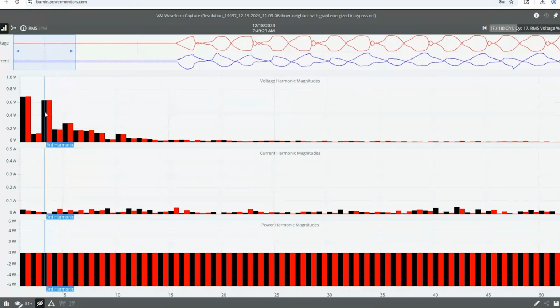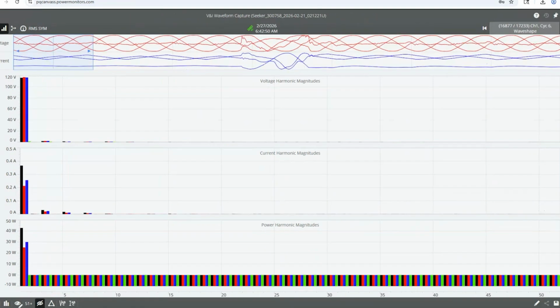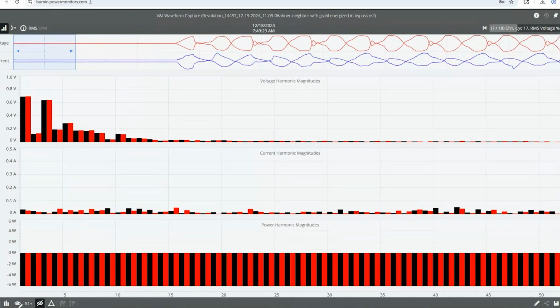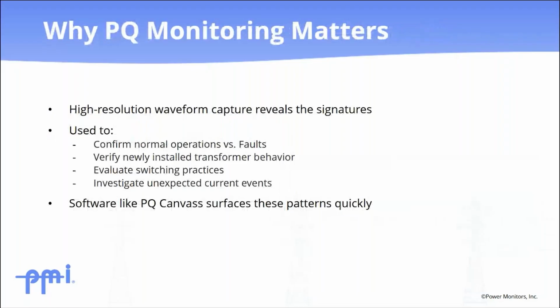You can look and see how much second and third harmonic content there is compared to the fault graph in figure 2 from the fault. And this second harmonic is kind of the dead giveaway right here. So if you take all these together, voltage magnitude, waveform symmetry, harmonic content, and event duration, you've got a reliable framework for telling a fault apart from a transformer energizing.